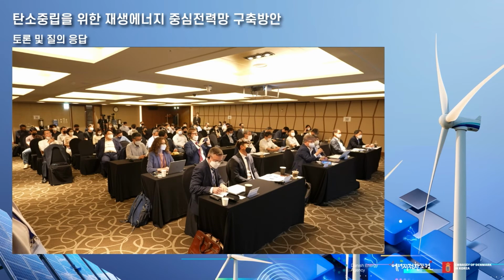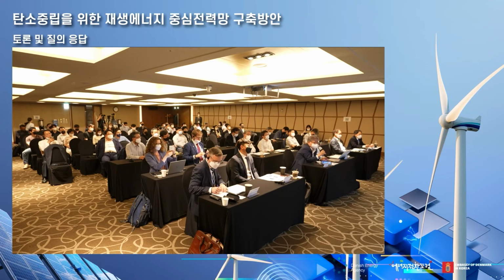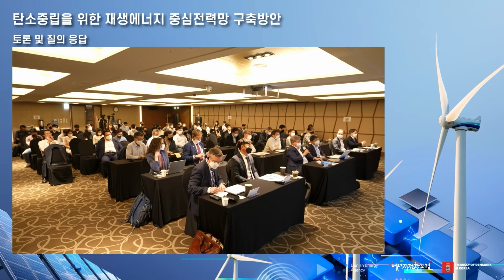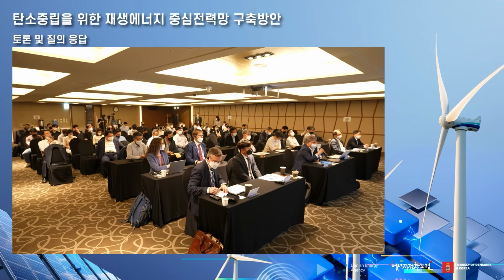In the case of Korea, compared to Denmark, the size is about twice as big, but the peak is about 10 times bigger than Denmark. So if you look at the energy density of Korea, simplistically put, we are about 5 times higher in terms of peak. And in the case of inverters, again, it's about 5 times bigger. You talk about the issue of inverters—we can design filters and overcome this challenge.